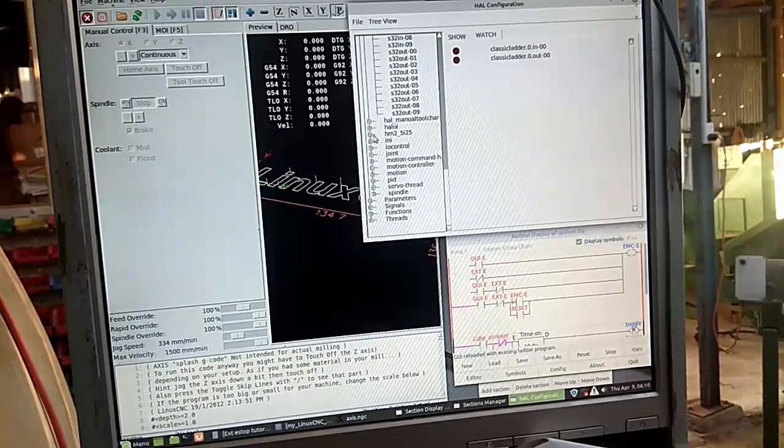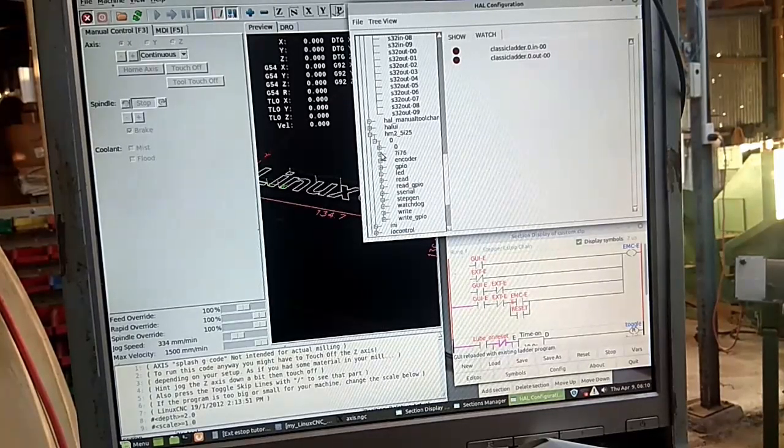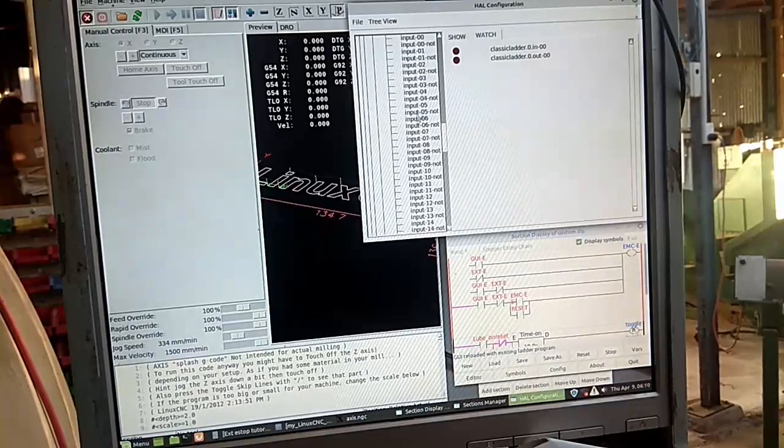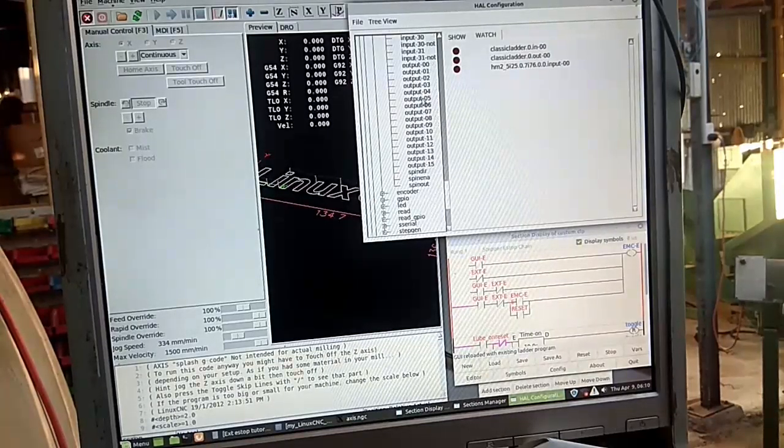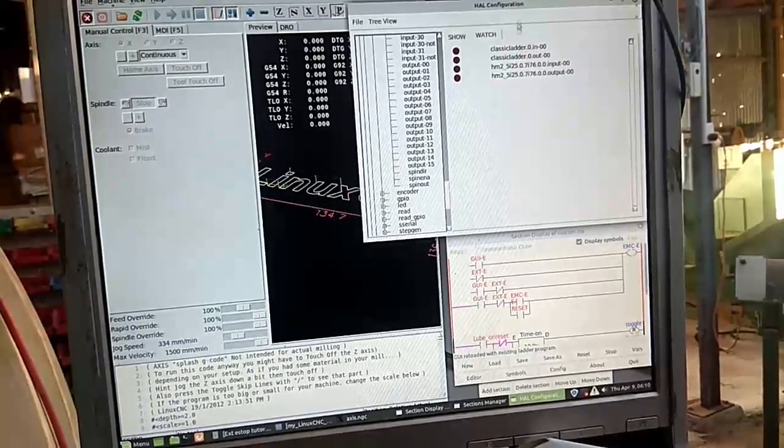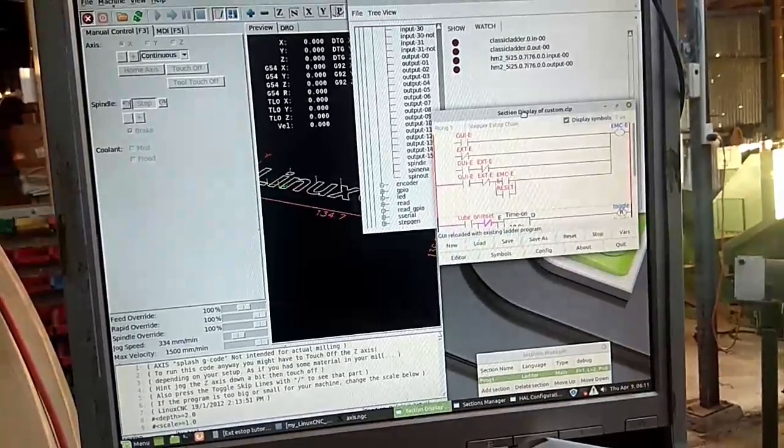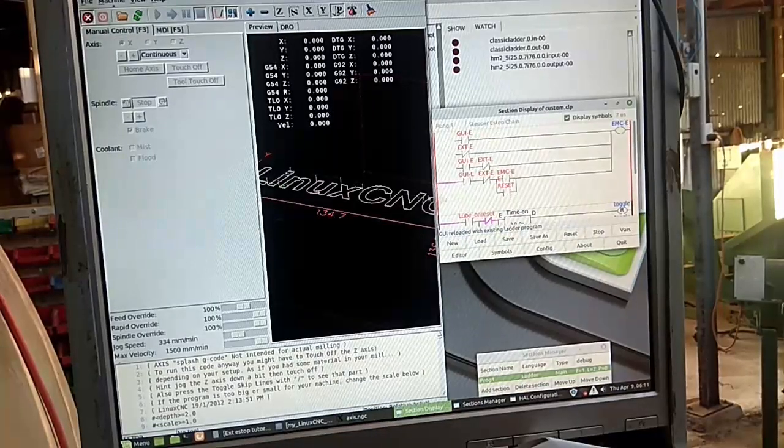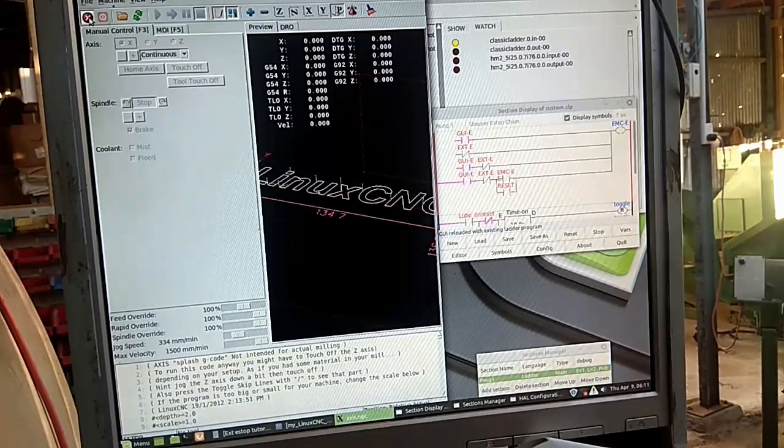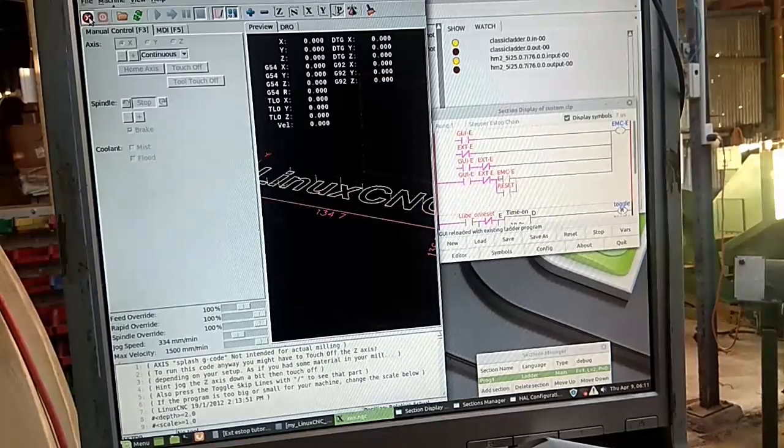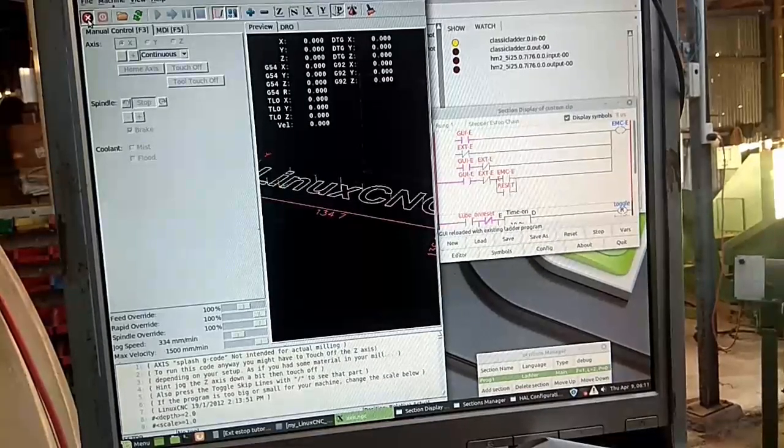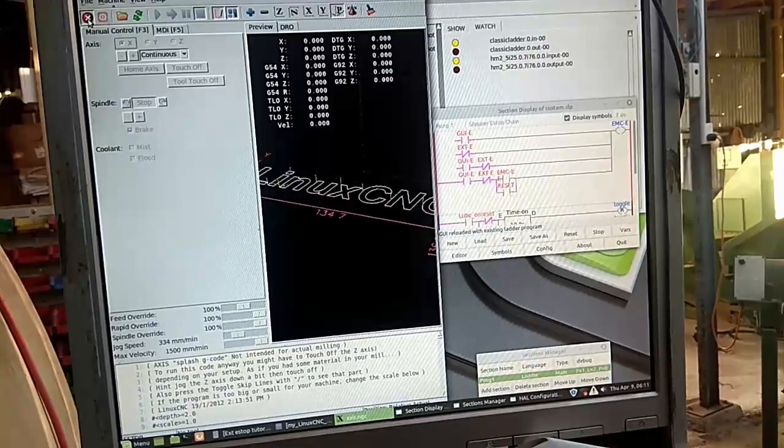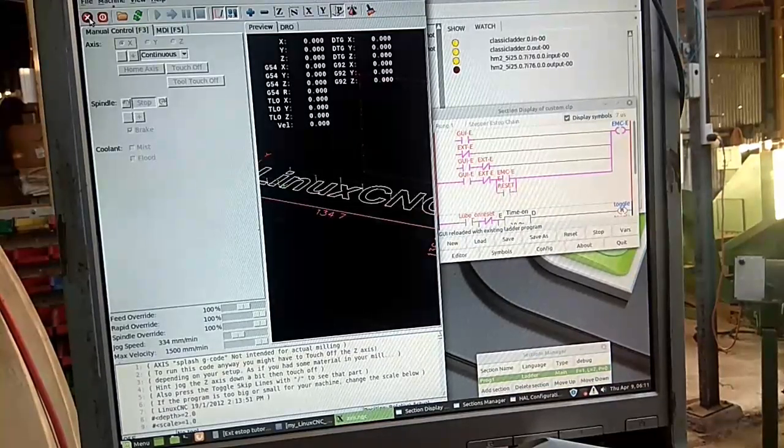Now if we open up some manual pins on the hm2_5i25, just keep clicking the pluses. Finally you get into here. Input zero is the e-stop in, and output zero is the e-stop out. So currently everything's killed. I just pushed my e-stop. If I push in the big e-stop, it kills everything. Then if I pull it out, then enable the main e-stop, it resets the thing and we're ready to go.